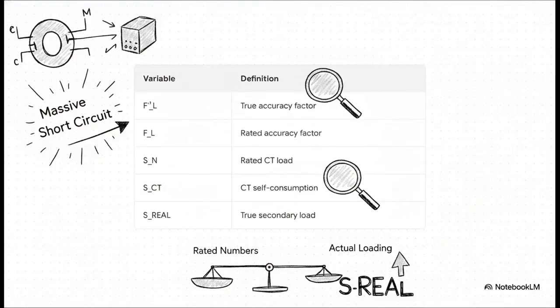The absolute crucial point here is calculating the true safety factor, which we call F'(L). See, instrument CTs are actually designed to deliberately saturate during a massive short circuit. This is to protect the relay's sensitive input ports. But to know exactly when that saturation is going to happen, we have to separate the CT's rated numbers from its actual real-world loading. We need to find S real, the true load at the CT secondary.